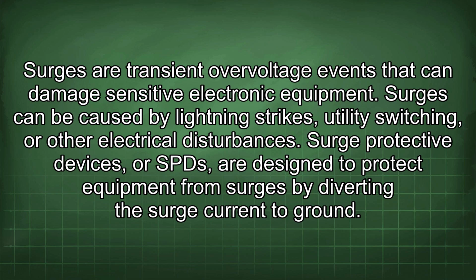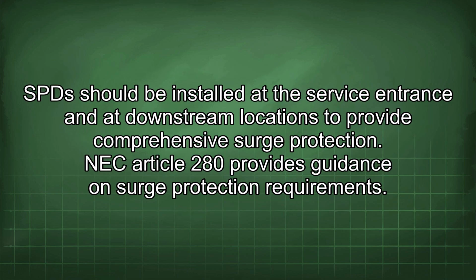Surges are transient overvoltage events that can damage sensitive electronic equipment. Surges can be caused by lightning strikes, utility switching, or other electrical disturbances. Surge protective devices, or SPDs, are designed to protect equipment from surges by diverting the surge current to ground. SPD should be installed at the service entrance and at downstream locations to provide comprehensive surge protection.